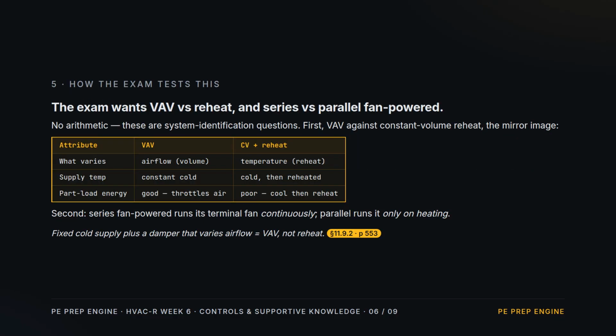How the exam tests this. No arithmetic, these are system identification questions. First, VAV against constant volume reheat, the mirror image. VAV varies the airflow and keeps the supply constant cold. Reheat keeps the airflow constant and varies the temperature. VAV is good at part load because it throttles air. Reheat is poor because it cools, then reheats. Second discrimination. Series fan-powered runs its terminal fan continuously. Parallel runs it only on heating. If a prompt gives you a fixed cold supply plus a damper that varies airflow, that's VAV, not reheat.